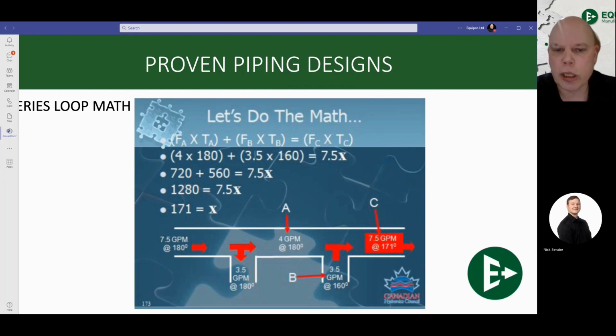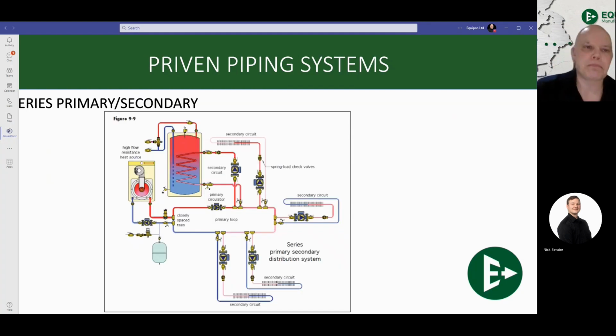Essentially, we use the laws of averages to figure out what your temperature is going to be by the time you have flow and you're supplying your return mixed in with your supply temperature. It's essentially the average, but there's a bit more math to that. If you want to check it out, do it, but this is the actual proven physical math that shows you what your temperature drop is going to be through a set of closely spaced T's in a circuit.